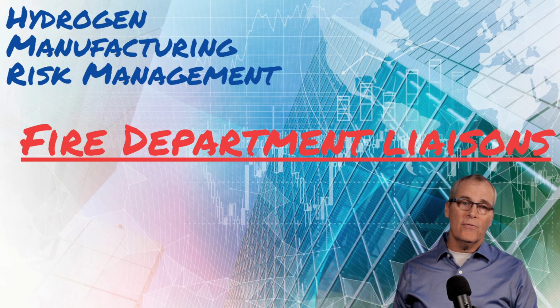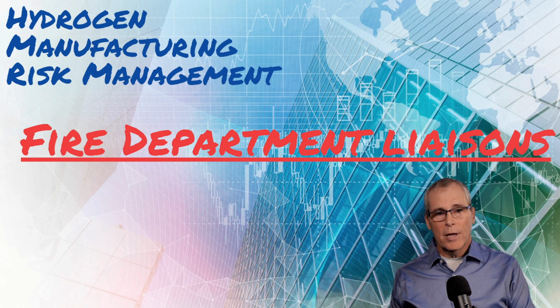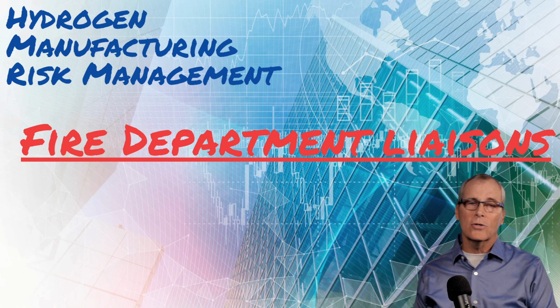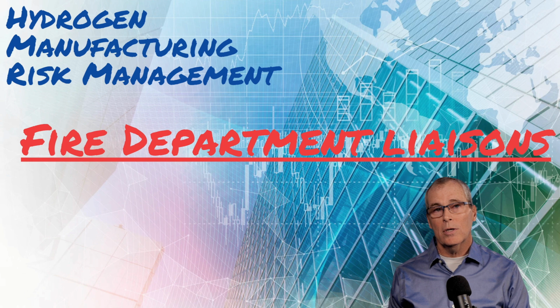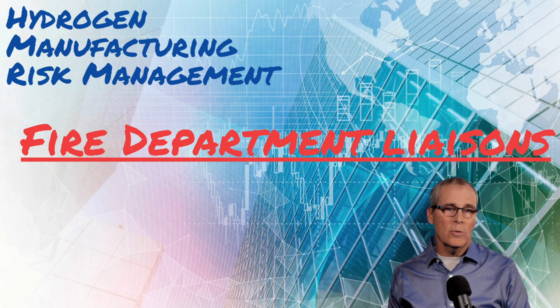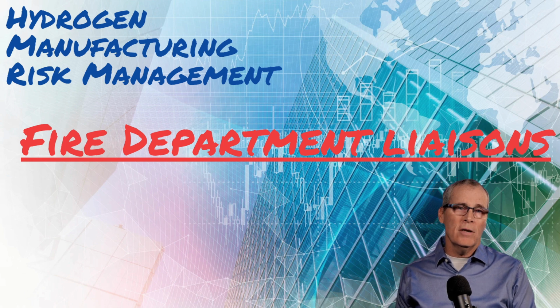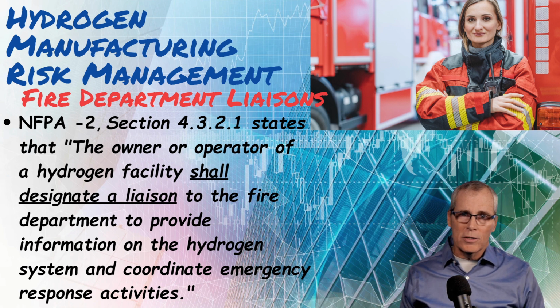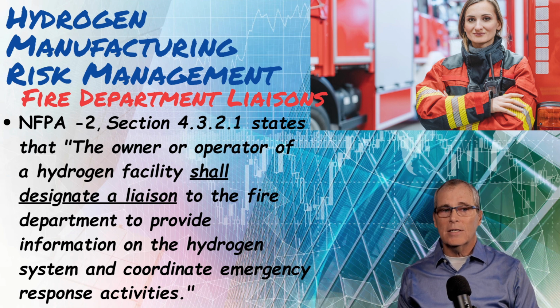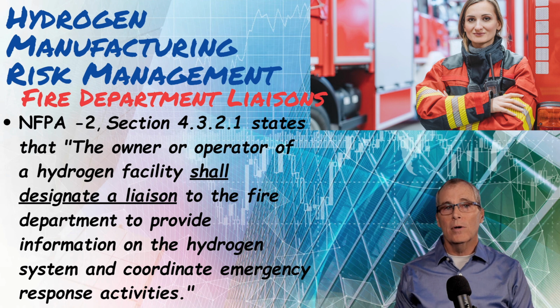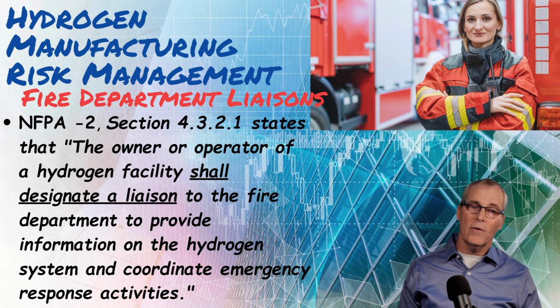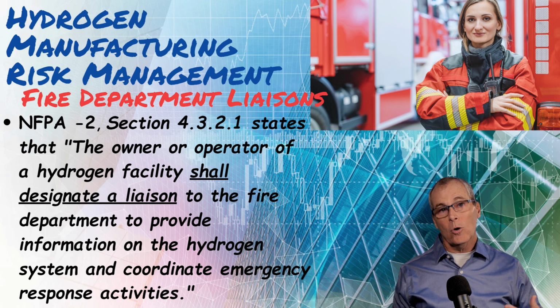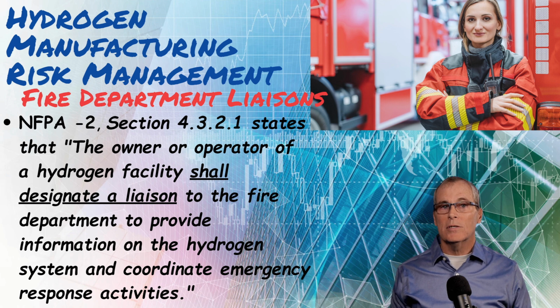NFPA 2 talks about fire department liaisons. Okay, fire department liaisons, it's a great idea. I worked in a company 20 years ago. We started this concept in the utility space, and we'll talk a little bit about how it applies in hydrogen manufacturing. But here it is. NFPA 2 says that you shall designate a liaison to the fire department. They're going to be there to provide information on the hydrogen and coordinate the emergency response activities.